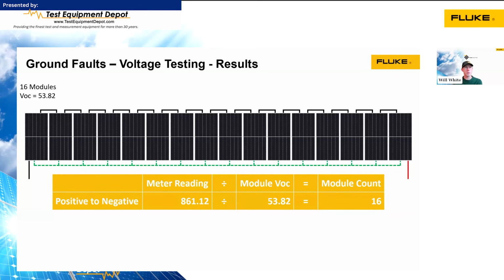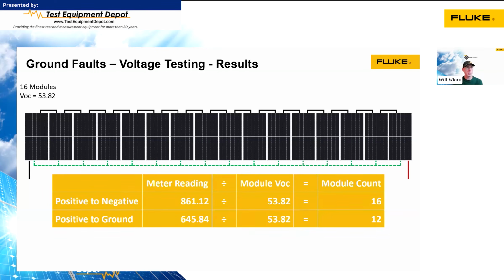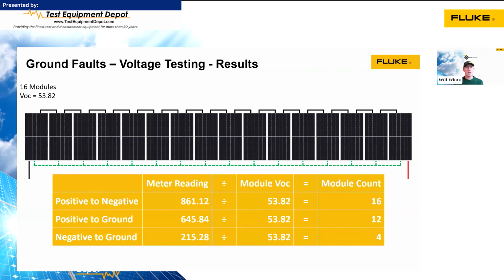If I take the positive to negative reading of 861 and divide that by 53, I get about 16 modules, which is the number of modules in my string. So that's what I would expect. Now, my positive to ground measurement was 645. If I divide that by 53, I'll get 12. And then if I do the negative to ground, 215 divided by 53 gives me 4. And this isn't going to be exact. You'll get decimal places, but it should be pretty close to an even number.